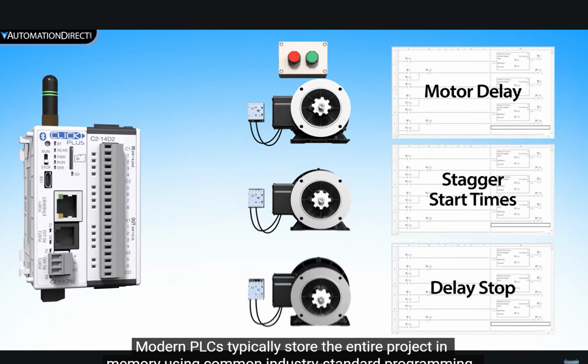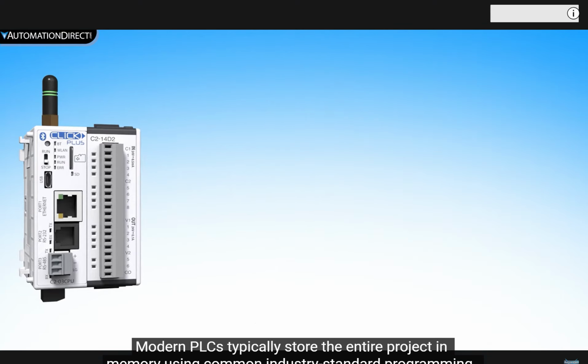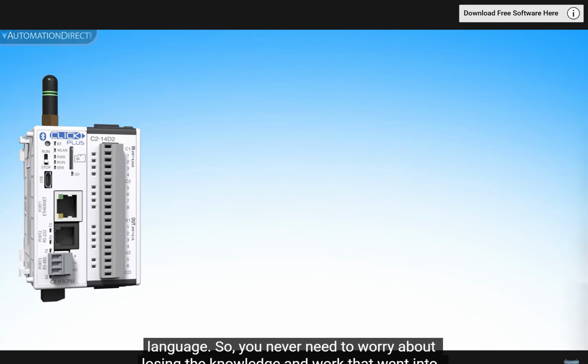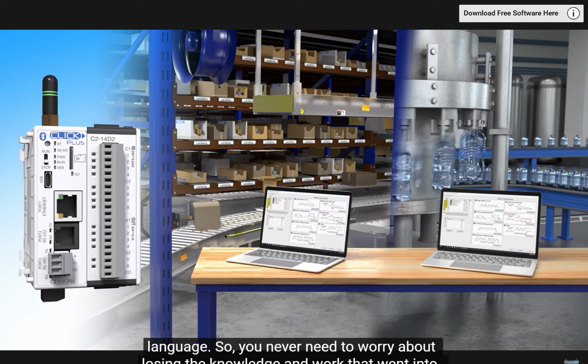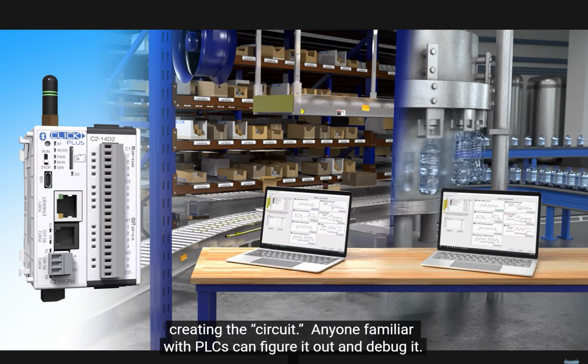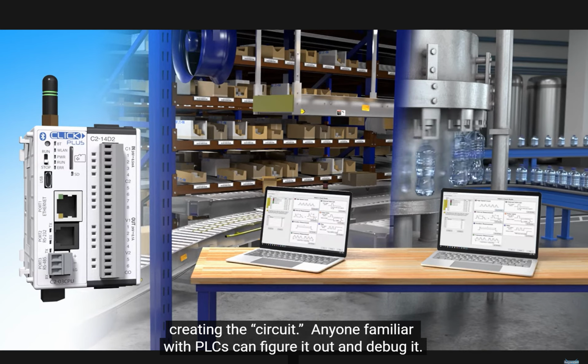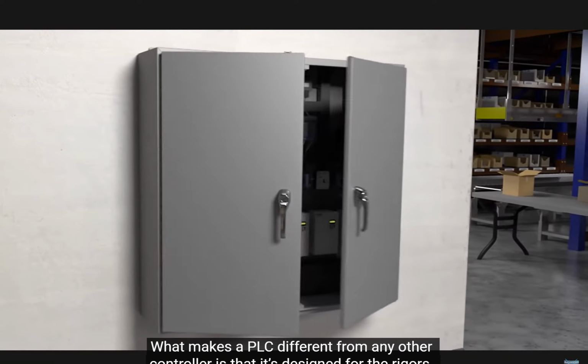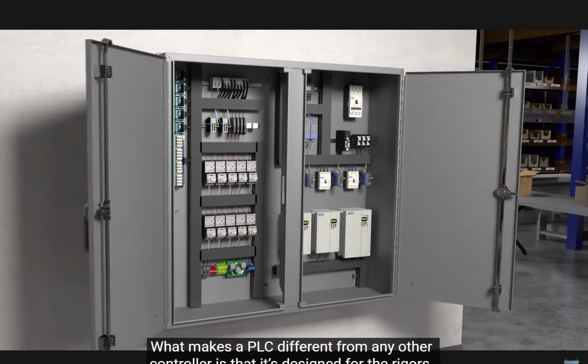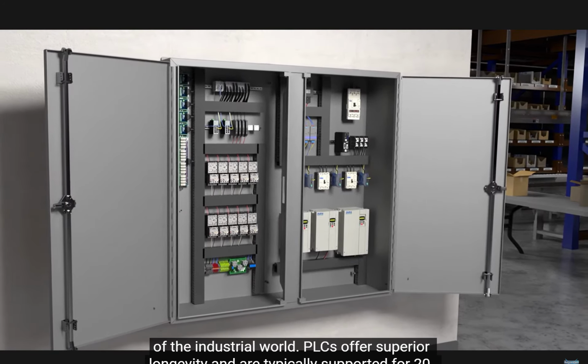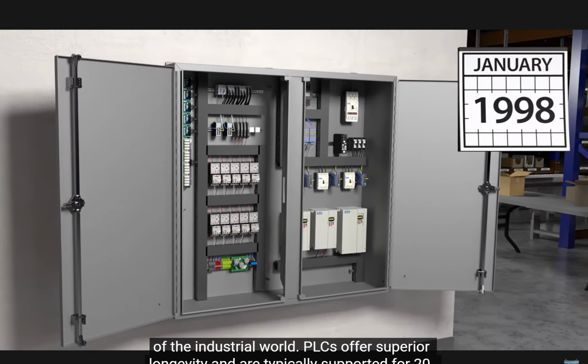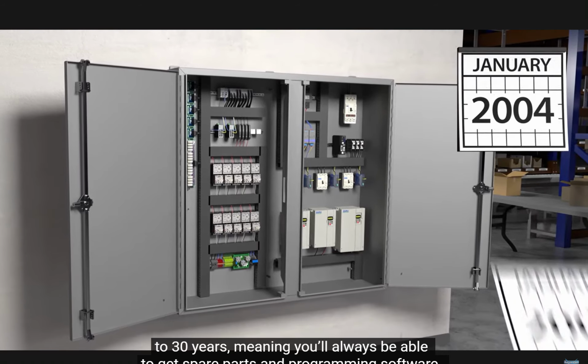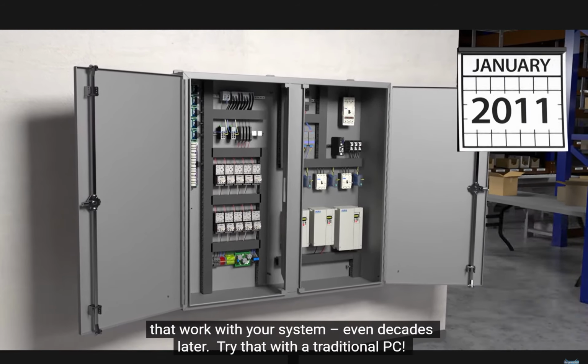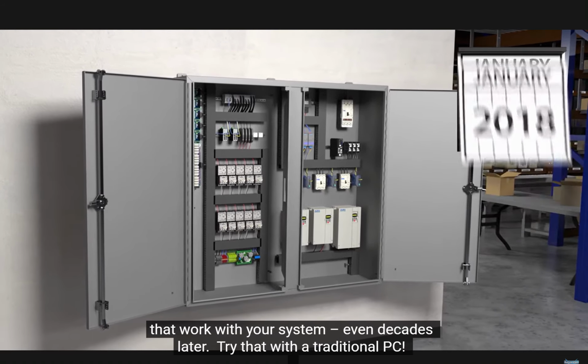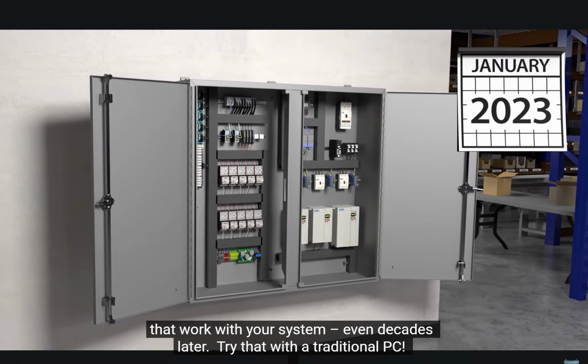Modern PLCs typically store the entire project in memory using common, industry-standard programming language, so you never need to worry about losing the knowledge and work that went into creating the circuit. Anyone familiar with PLCs can figure it out and debug it. What makes PLCs different from other controllers is that they're designed for the rigors of the industrial world. PLCs offer superior longevity and are typically supported for 20 to 30 years, meaning you'll always be able to get spare parts and programming software that work with your system even decades later. Try that with a traditional PC.